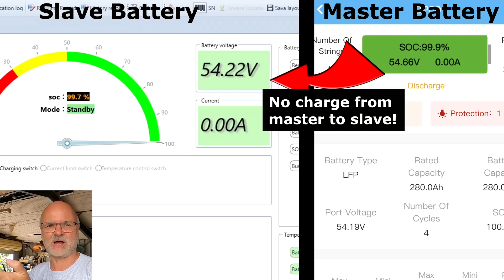We now have over 0.4 volts difference between the master and the slave, and there's no equalization current or anything going on because charging is still turned off in the master. I found it weird because the master is actually a higher voltage than the slave, and the slave accepts charging. Why is it not charging from the master to the slave then? But it's not doing it, there's nothing going in between the batteries.